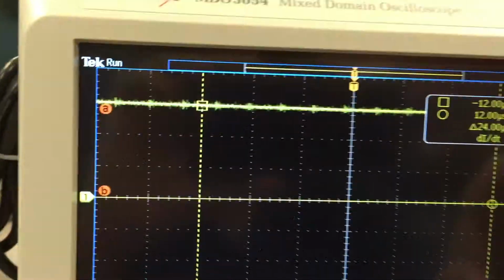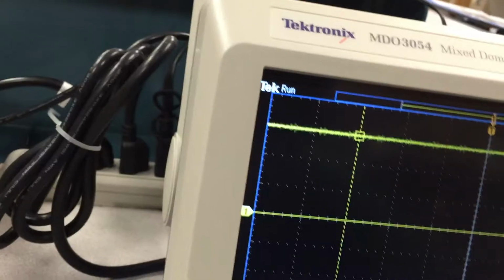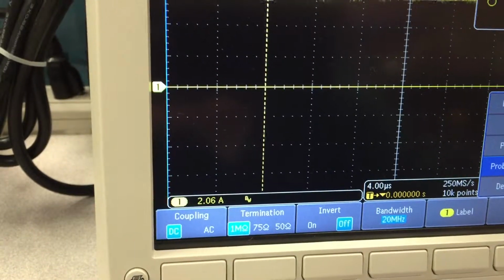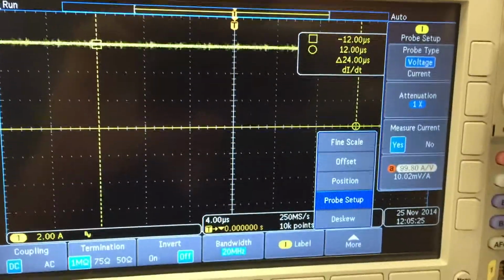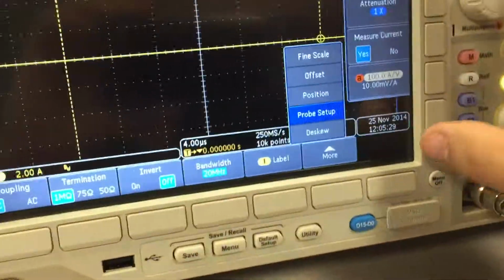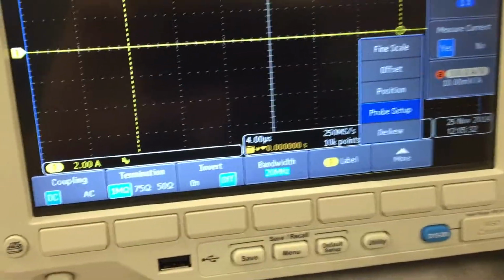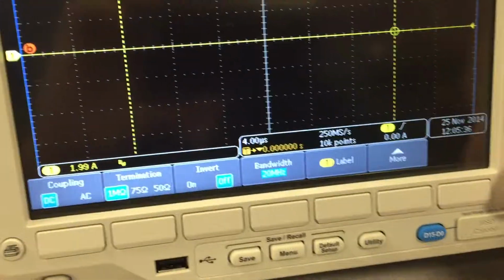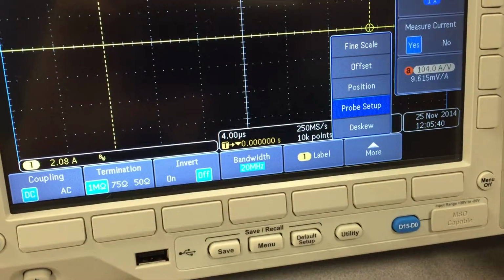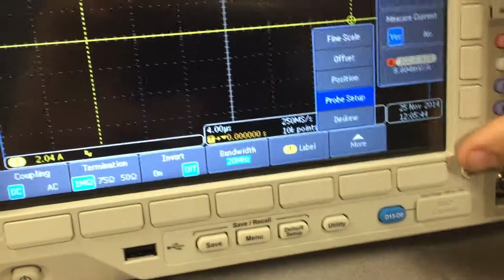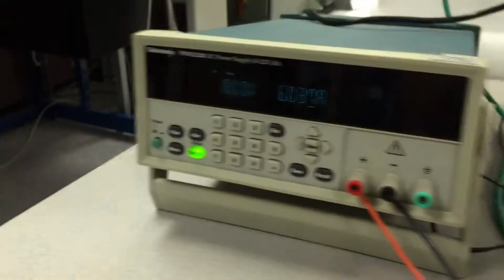And if we look at our delta measurement now, it's about 5.98 amps versus about 6.0. Let's see if we get that a little bit closer. That's pretty darn close. So we're saying about 6.038 amps against 6.038 amps. So that puts us pretty darn close to calibrated. So we're dealing with about 2.04 amps per division with this probe.